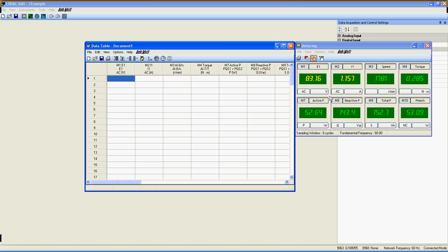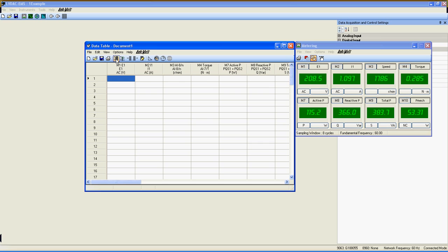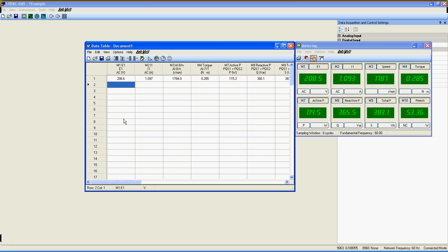Let's start the motor. As you see, loads of values appear on these meters, and writing them down one by one would be time consuming. Since the data table is all set, just click here on the Record Data button, and every value in these meters will be registered in the data table.